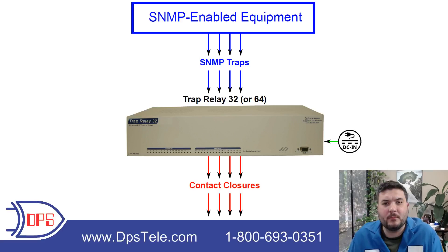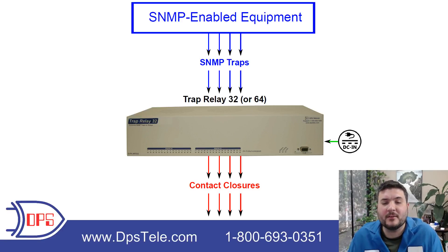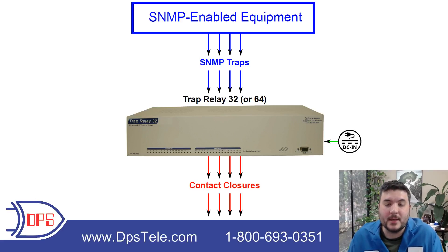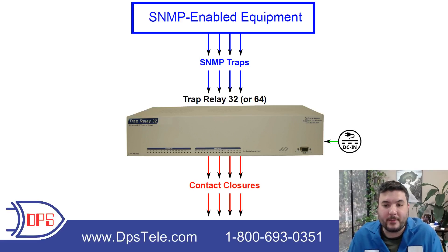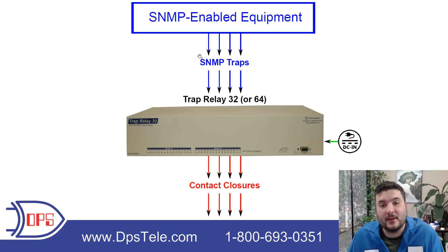But the world is going to be more protocol-based. You see more and more equipment nowadays where it doesn't have any contact closures at all — it only uses a protocol like SNMP, Modbus, or DNP to output alarm data. So how can we bridge the gap? Well, this trap relay device you see in the middle of the diagram here is developed to translate SNMP to contact closures.